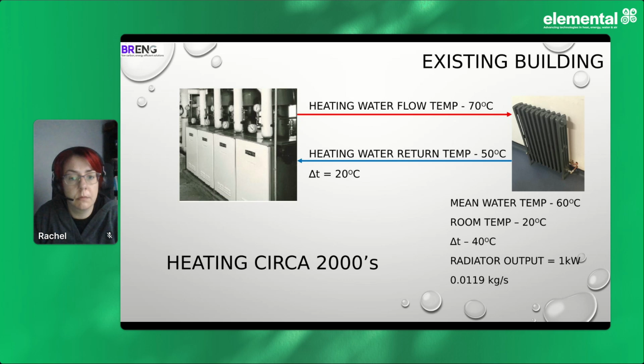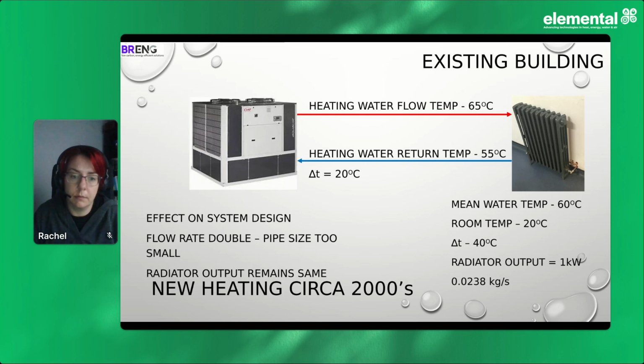Back in the 2000s, everybody started changing the temperature differences on the heating system. Now this causes us not concern, but it causes us a different challenge. So they worked at a different temperature difference, and because they worked at a different temperature difference, the pipework became smaller. So that worked at a 20 degrees temperature difference. And when we go to air-to-water heat pumps to use the existing infrastructure, what we found is we're working on a 10-degree difference. So technically, the pipework is actually half the size we really need it to deliver what we need.